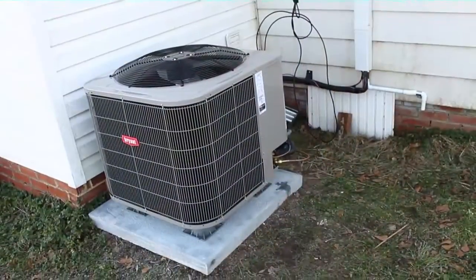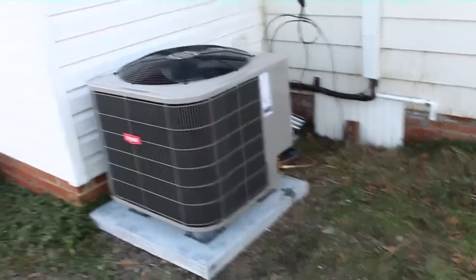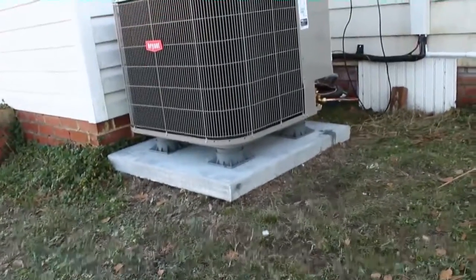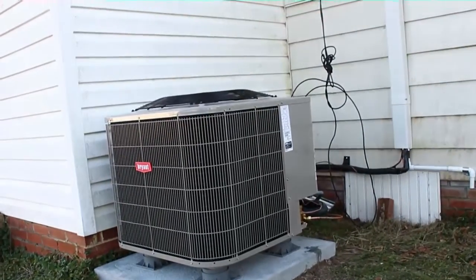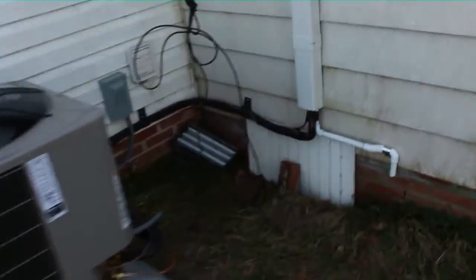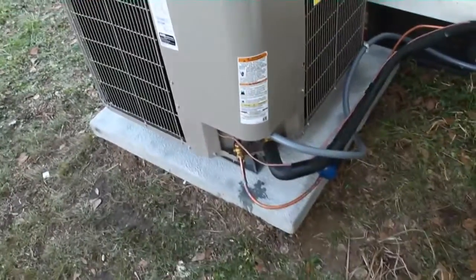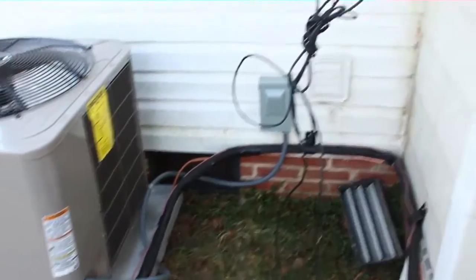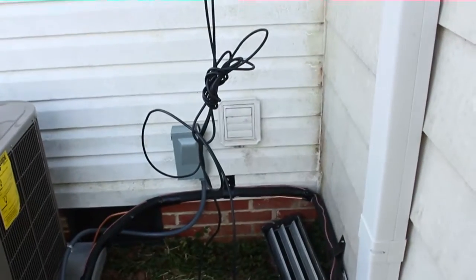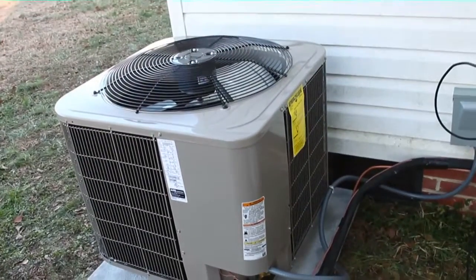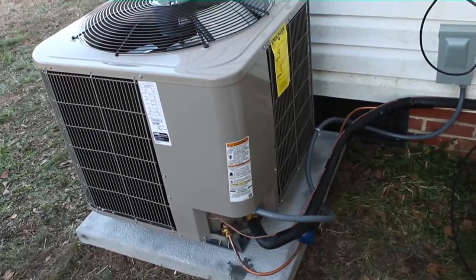Alright guys, here's our Bryant heat pump. Got it on the old risers there, about 3 inches off the ground. Everything's looking pretty good and square. It's our line hide. We ran our lines around the side, giving us a nice service area coming back this way. So there's plenty of room, you don't have to put it up against the house and sandwich anything in, so it's tough to work on, for our disconnect. Keeping it out of the way of our dryer vent as much as possible. And our crawl space hole, everything came out good. Tomorrow we're going to come in the morning and start everything up and do some of our testing.